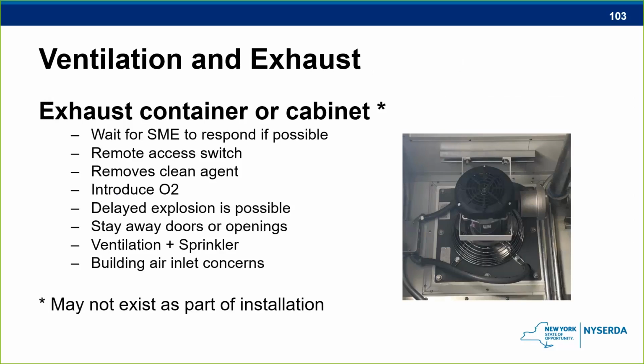Ventilation and exhaust. This is not required for lithium-ion. It is required for lead acid batteries, and we talked about that. During normal operation, lead acid batteries will actually off-gas some hydrogen. If that hydrogen starts to build up inside and it gets to 25% of its lower flammable limit, this exhaust fan should kick on, pulling that stuff out.